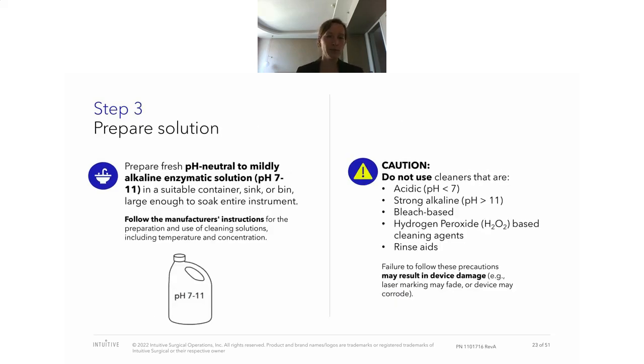Then prepare the solution. Again, it depends on what detergent you're having. We recommend something that is in between a neutral and mildly alkaline pH, which is 7 to 11. And we do caution against the use of acidic cleaning agents, which means that they have a pH lower than 7, strongly alkaline detergents, meaning they have a pH larger than 11, and bleach-based and hydrogen peroxide-based cleaning agents. And then also rinse aid is something that we caution against because it has an effect on the instruments and can lead to damage.